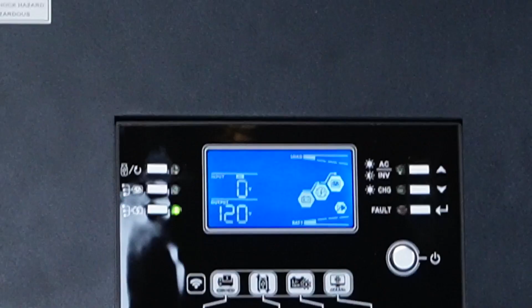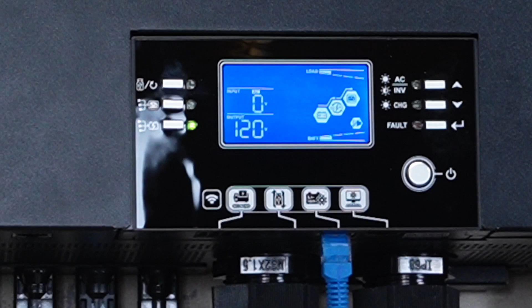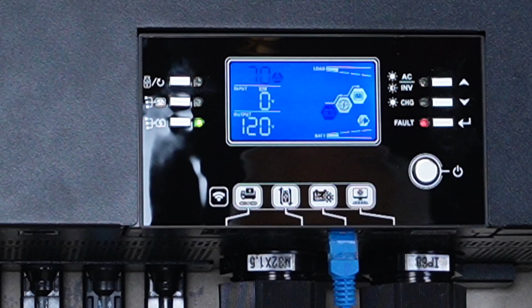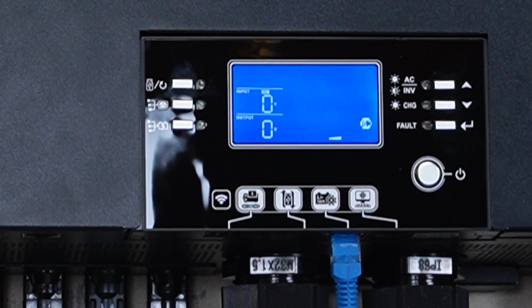So just what I was worried about, the inverter started flashing a fault, and then it actually shut down and turned off. But we have approximately 18 to 20 amp hours left. So I'm not really sure why, the battery voltage is actually at 50.5. So why would it shut off? And it's giving me an error code 70. Let me look up and see what that is.